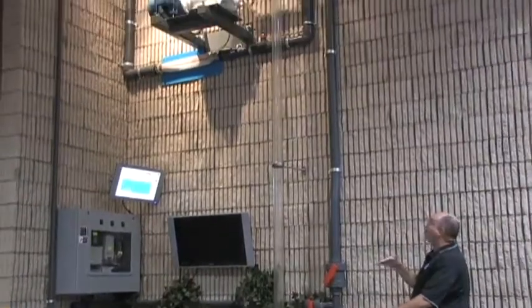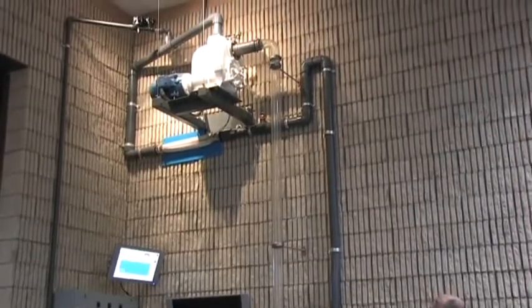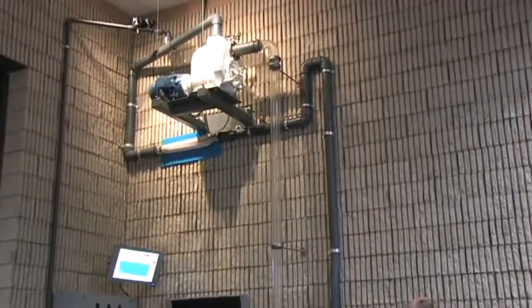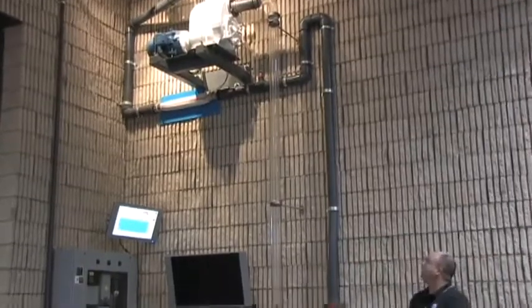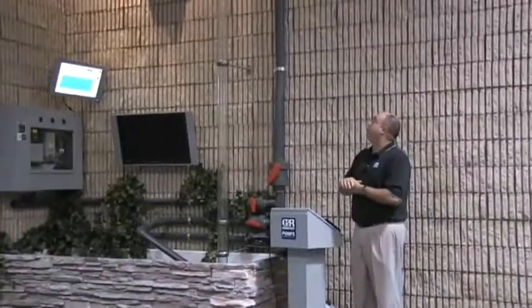You can hear it kind of settling out, where the pump has now broken siphon, and we're in a situation where now we have a dry suction leg, a 15-foot suction lift, but now we only have a half a casing of liquid in the pump.